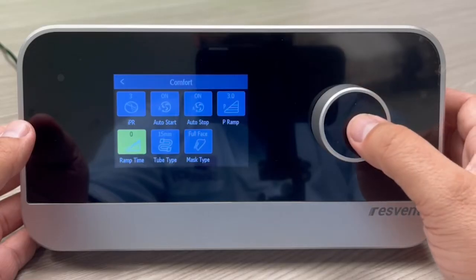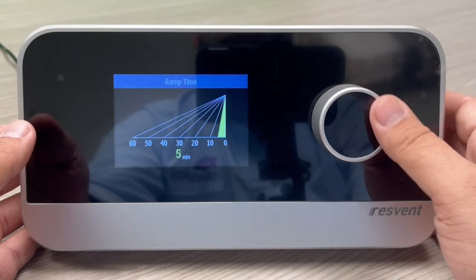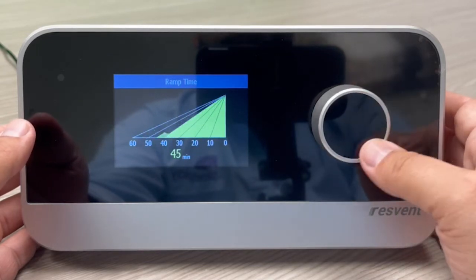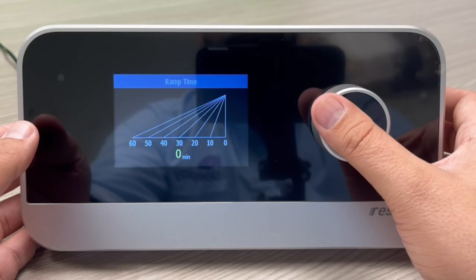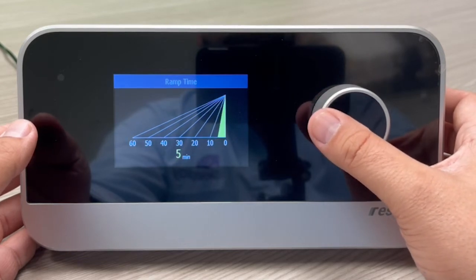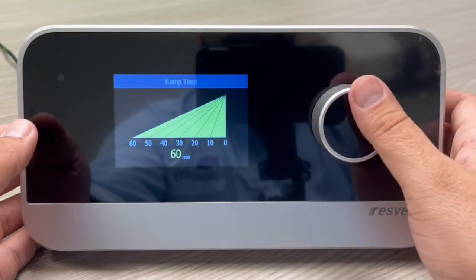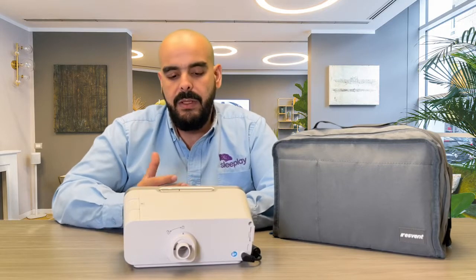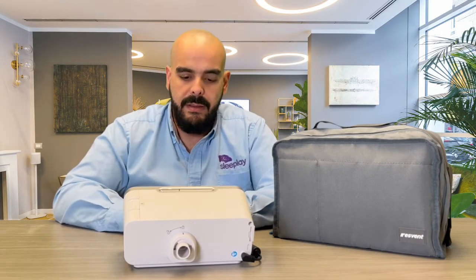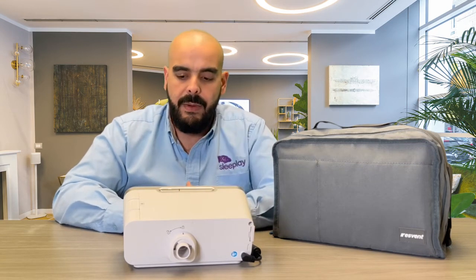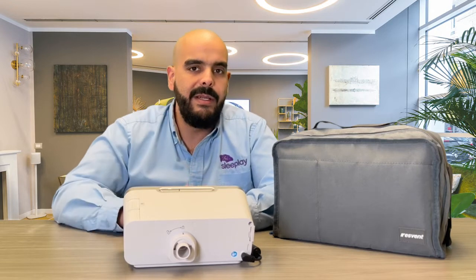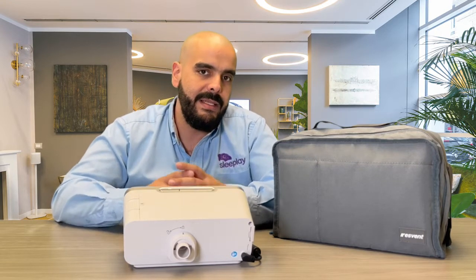The next one over is the ramp time. Now the ramp time here, you can go up to 60 minutes and you can go as low as off, of course. Typically, I don't recommend such a long ramp. Usually 15, 20, 30 minutes is pretty much all you need. When you go to those extended ramps, your AHI can stay a little bit higher because you're not getting the adequate therapy as fast as you need it.